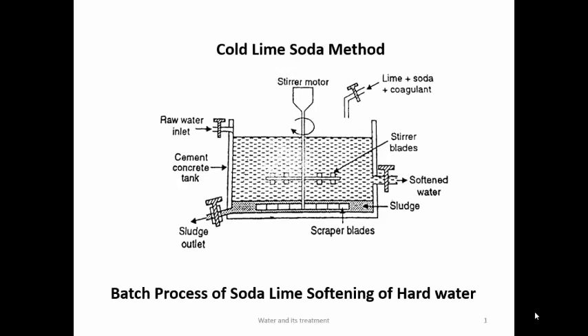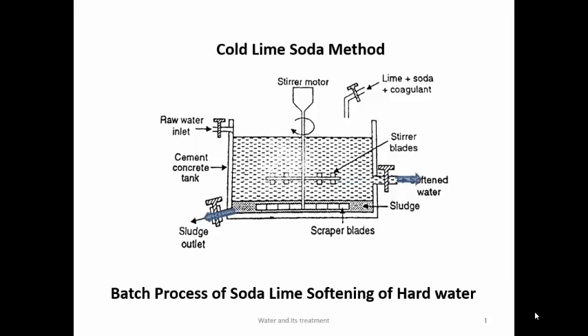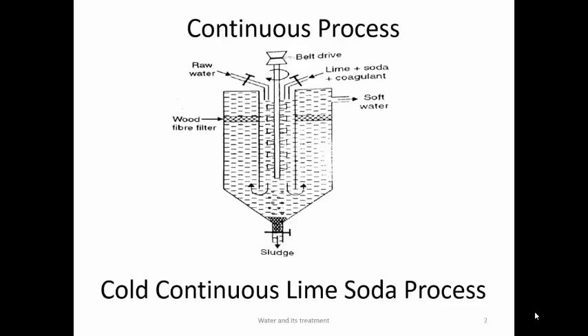In the lime-soda method there are two variants: cold lime-soda method and hot lime-soda method. In the cold lime-soda batch process, raw water is added from one inlet and lime, soda, and coagulant are added from another. The coagulant gathers the precipitate and settles it to the bottom. A stirrer motor mixes the contents. After reaction, the precipitate is removed as sludge from the bottom outlet, and softened water is removed through a filter bed. Two cement concrete tanks are constructed side by side and used alternatively. Residual hardness is around 30–50 ppm. The major drawback is that batch process is time consuming.